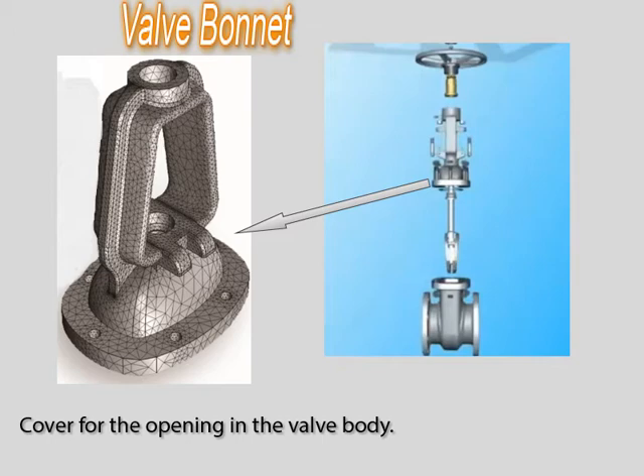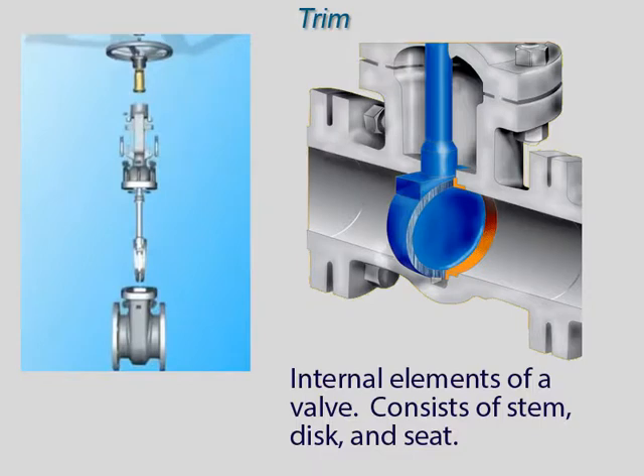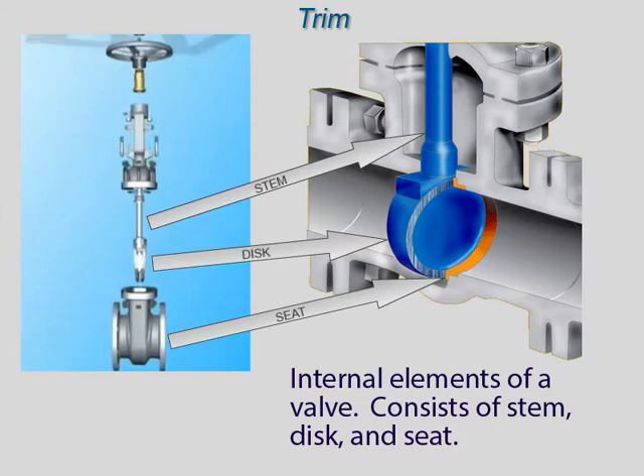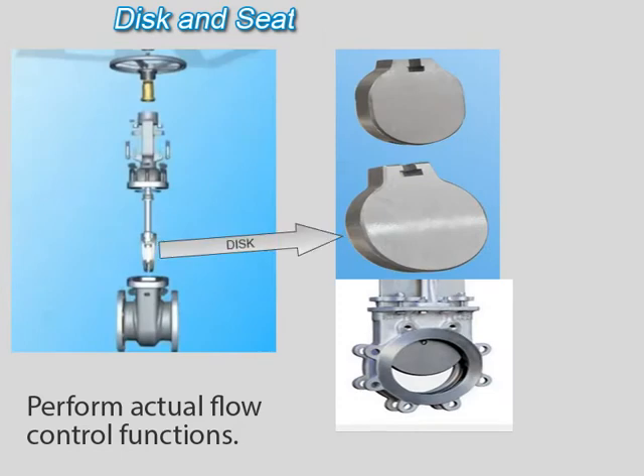The bonnet is the second principle pressure boundary of a valve. It is cast or forged to the same material as the body and is connected to the body. The internal elements of a valve are collectively referred to as the valve trim. This is the portion of the valve that moves and controls flow. The elements that make up the trim are the disc, seat, and stem. The disc and seat perform the actual flow control functions of the valve. The disc has a machined seating surface that meets with the valve seat to provide a positive seal when the valve is closed.